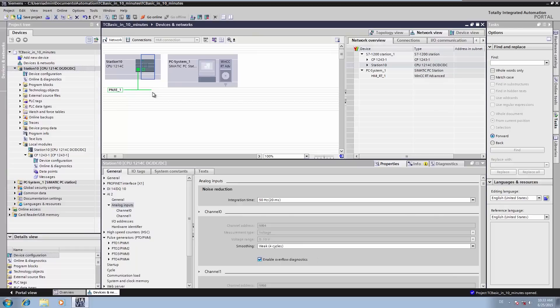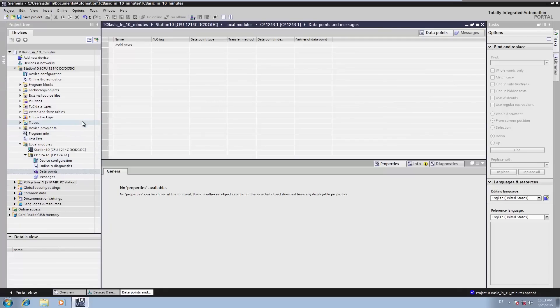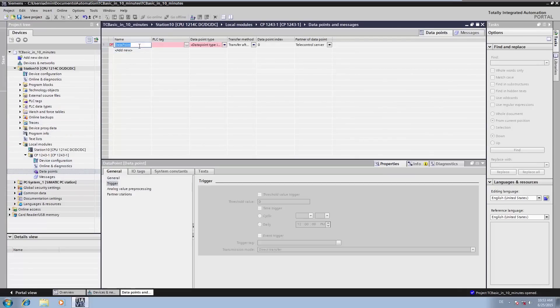However, no process data is being transferred yet. In order for our station to transfer process data to the control center, we switch to the so-called data point editor. There, the data points or process values to be transferred are simply linked with the PLC variables. In order to import and transfer the digital input as a message to the control center, we specify a data point of the type digital input.